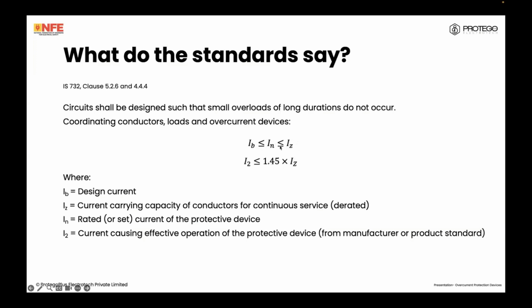However, in between, you have to have a protective device. So if I have a 13 ampere load, which is our design current, IN can be 16 amperes, but the current carrying capacity under continuous service, which is derated, has to be greater than the value of IN.